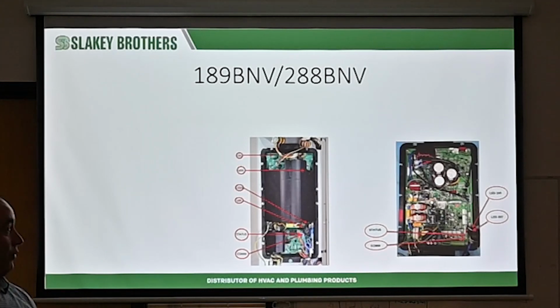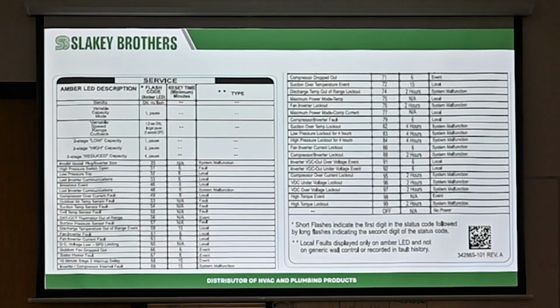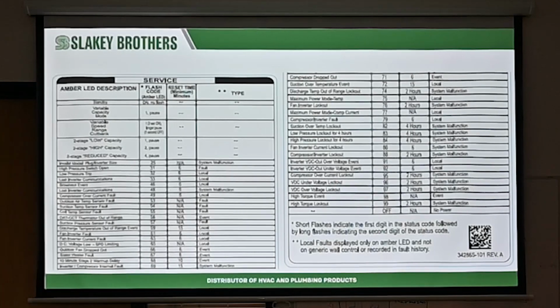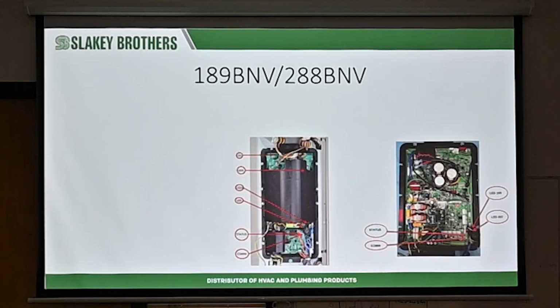The first time I ever opened up one of these units was a 5-stage heat pump out in the country. I opened it up like 7-8 years ago, and I was like, what the hell? I know a lot about evolution, and I knew a lot about infinity. Same exact thing. I opened it up, and I was like a freaking monkey, scratching my head. Those had a little contactor to power up the board. All the contactor did was close and power up the system. I was over here pushing the button, scratching my head, like, it won't work. I don't know. It's really intimidating. Looking at this junk right here, it can be very intimidating.